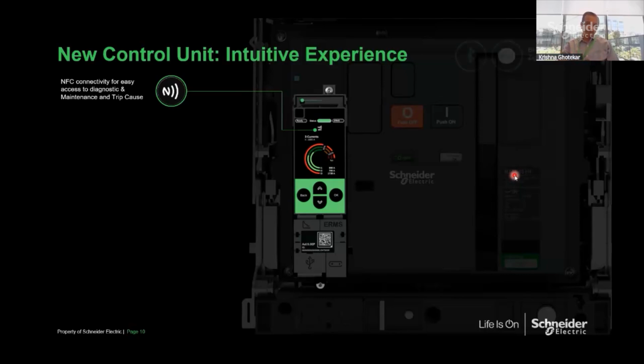Then as you can see here, if it's a wireless type, we will add on top of the trip unit, and it will be green in color. It will additionally have Bluetooth connectivity, so that you can connect with our application called EcoStruxure Power Device, which is mainly for facility management. Again, it's freemium. That means you can download it from iOS and Android, and it just needs a one-time registration. Or if you are already registered in any software, you can use the same credentials, so that you can communicate and download the parameters from the breaker using Bluetooth.